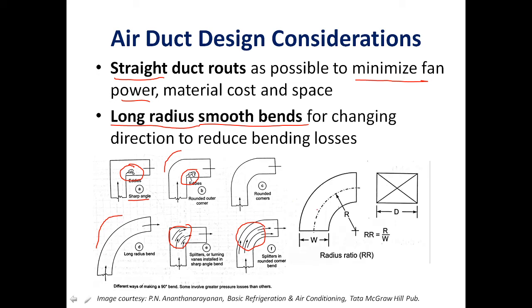The important design parameter for bends is the radius ratio, defined as the ratio of the radius of the bend to the width of the bend. A radius ratio of 1.5 is considered good for minimum bending losses.